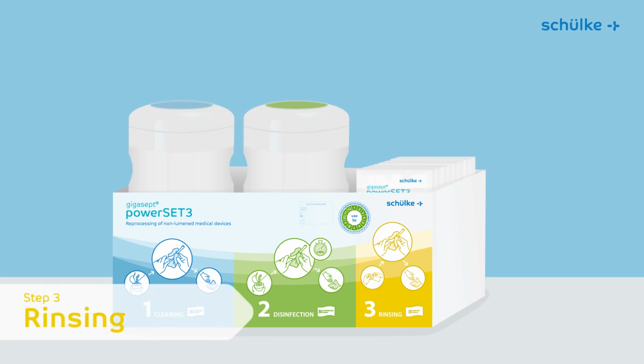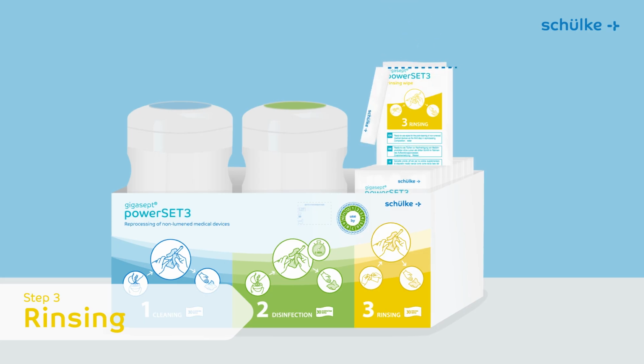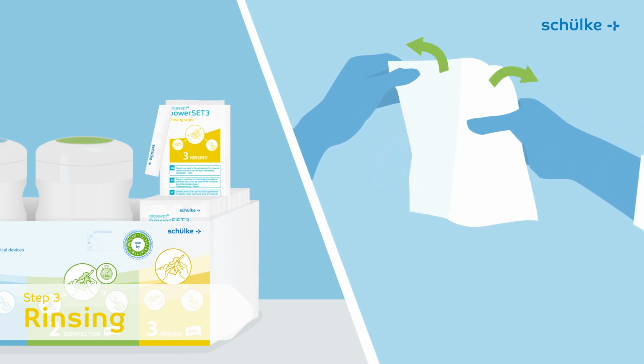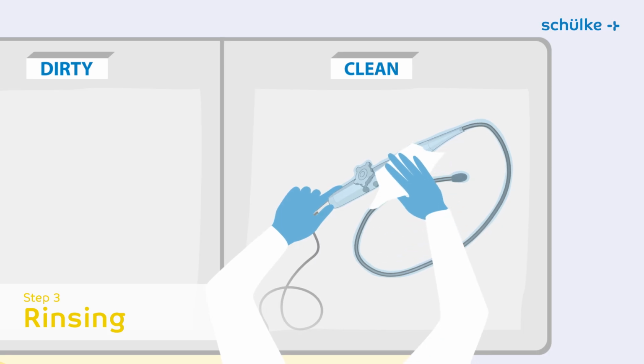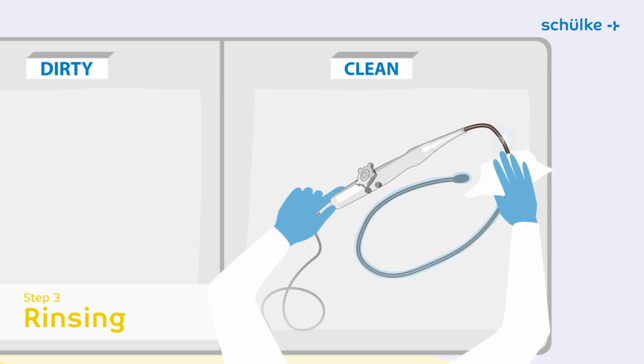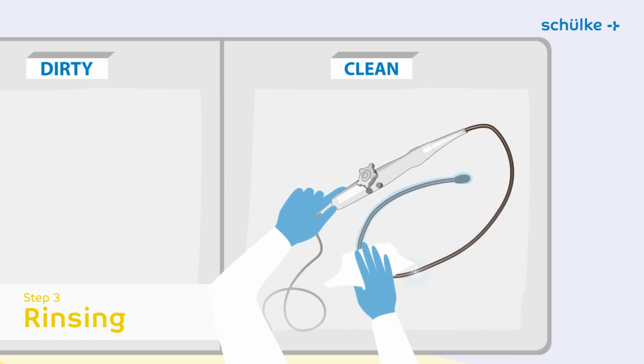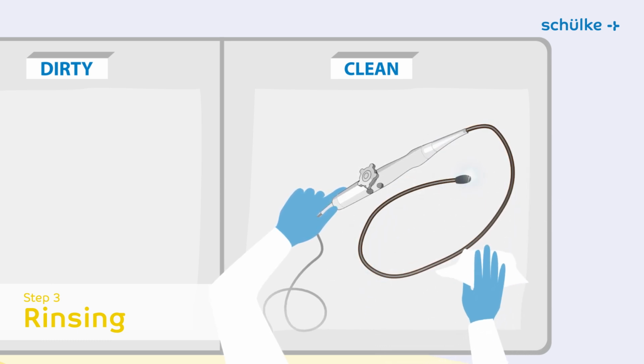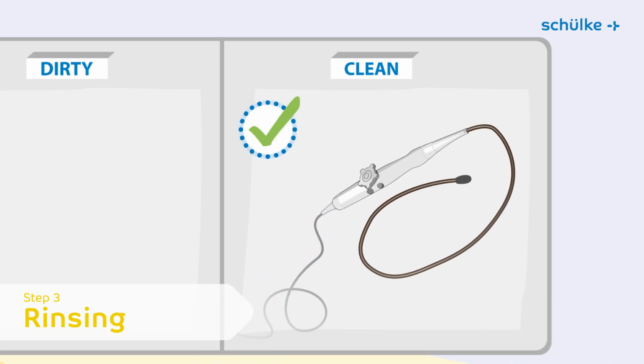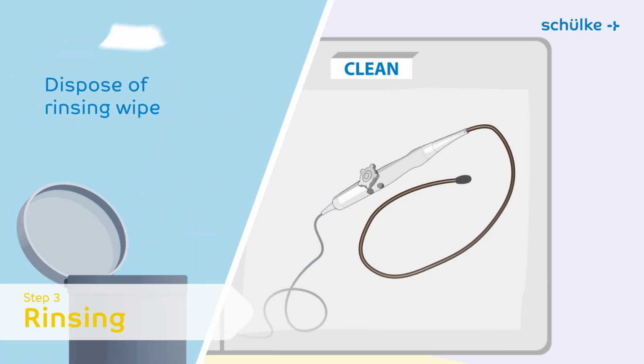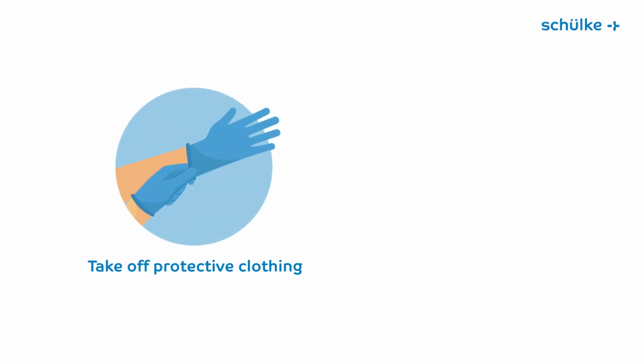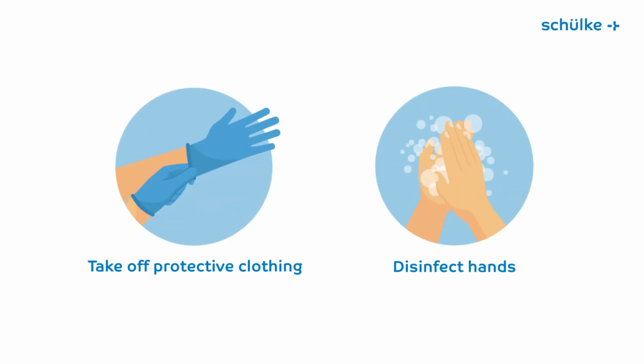The last reprocessing step is rinsing. Each gigasept powerSET3 rinsing wipe is individually packaged. Open the packaging at the marked point. Remove and unfold the wipe. Wipe the medical device thoroughly until all surfaces are completely wetted and possible residues of the disinfectant are removed. The reprocessing is now complete. Dispose of the used rinsing wipe in accordance with local regulations. Take off protective clothing and perform hand disinfection.